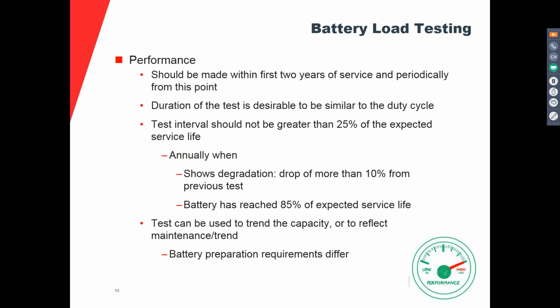Once the battery shows degradation, for example, if the battery capacity drops more than 10% from the previous test, we need to start testing annually. Or whenever the battery has reached 85% of the expected service life, we should also start doing the test annually, because from this point on, the battery is expected to drop in capacity faster than it did in the early years. So there is like a knee point in the behavior of the capacity of a battery. It starts degrading, and then reaches a point where it starts dropping very fast. And that is expected to be around 85% of the life of the battery.